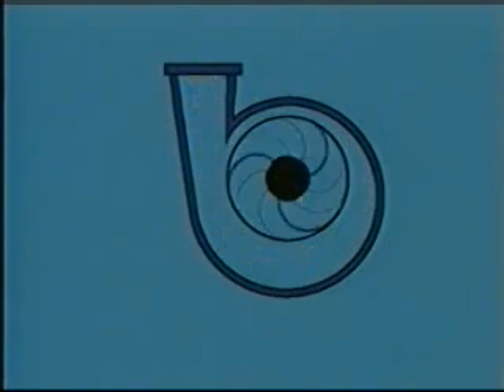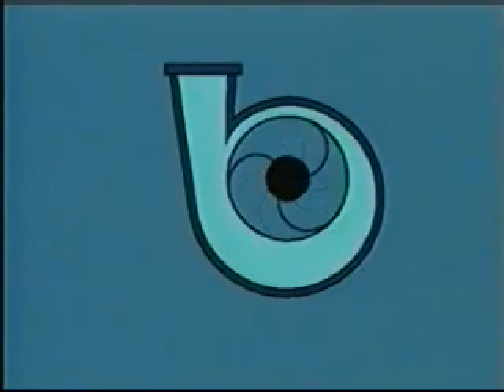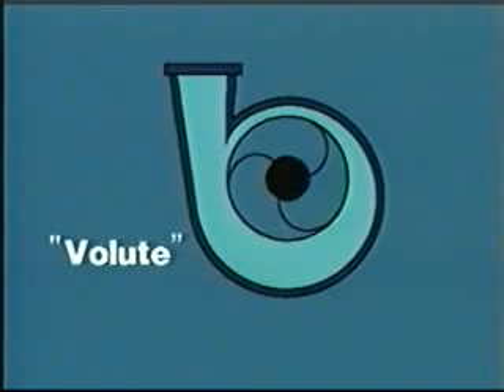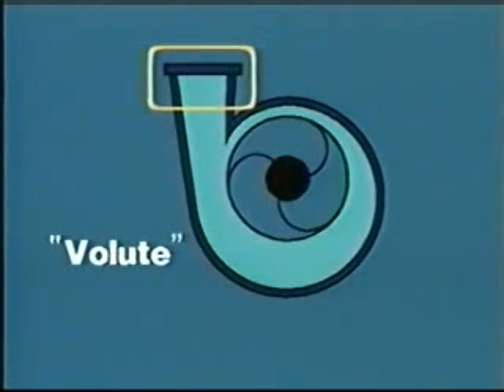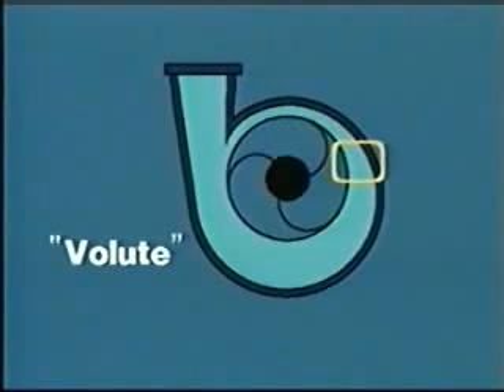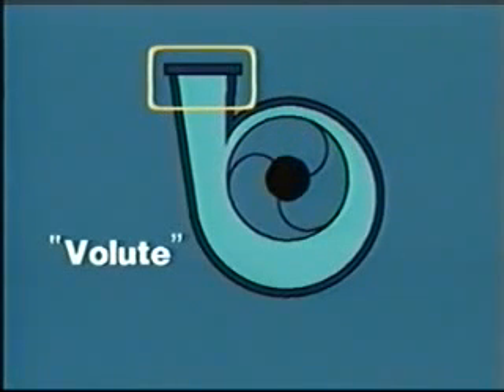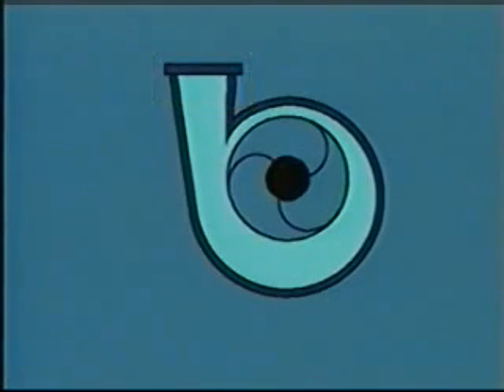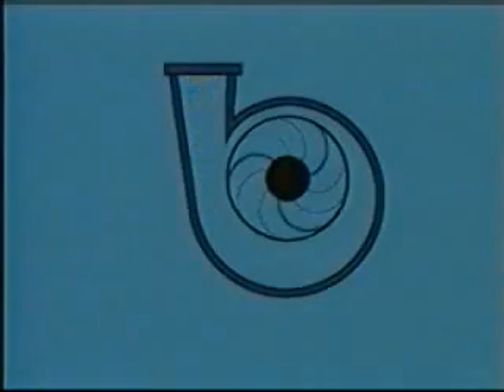It enters a specially designed area of the casing known as the volute. The volute is wider at the discharge nozzle than where the fluid leaves the impeller. There's more space, which causes the fluid to slow down. Its velocity decreases. The fluid gives up some of its energy. But that's not all. Energy just doesn't disappear. It's converted into pressure, and that pressure forces the fluid out of the discharge nozzle. The fluid leaves the pump at a higher pressure than when it enters.